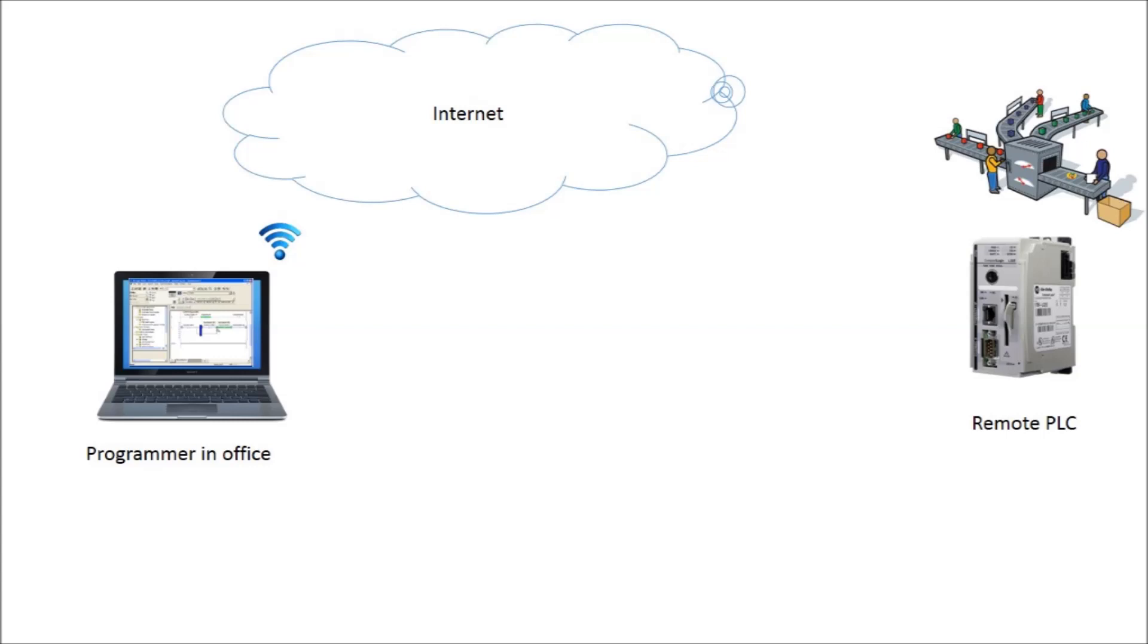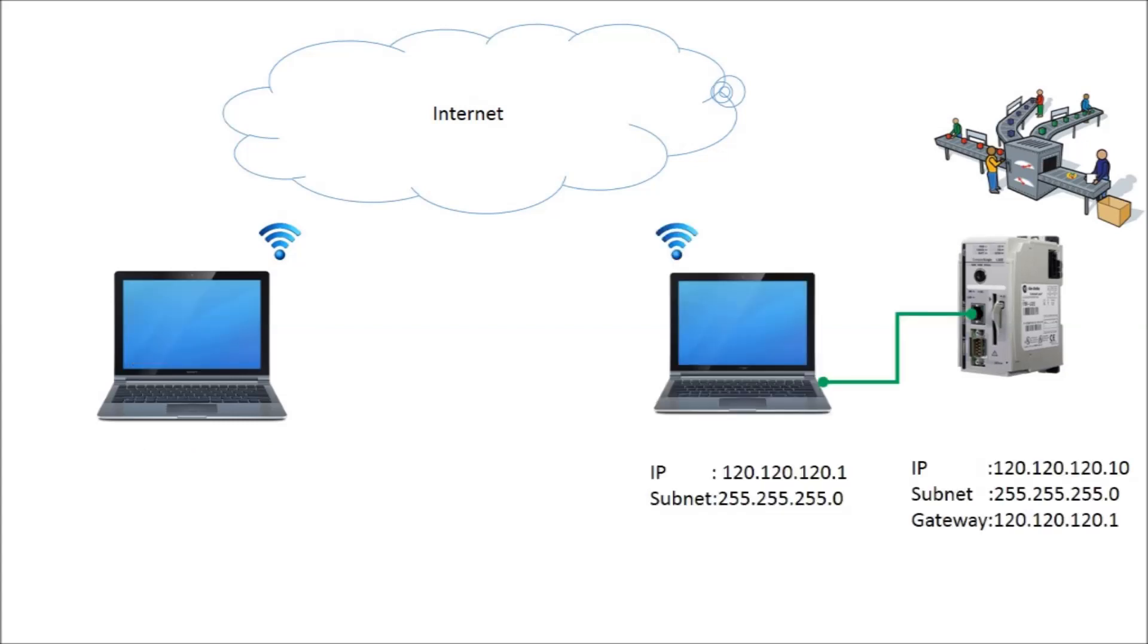To do so, we first ask someone in the plant to connect their computer to the PLC by means of an Ethernet cable. It is assumed that this computer has access to the Internet. As a prerequisite, the PLC must have a configured static IP address, a subnet mask, and a default gateway address, which are normally done.